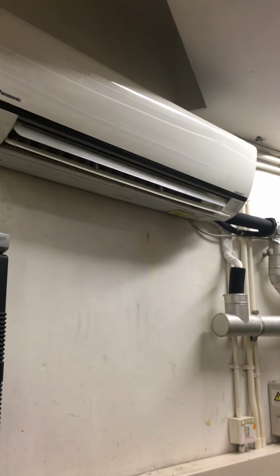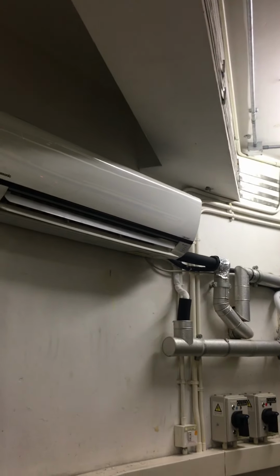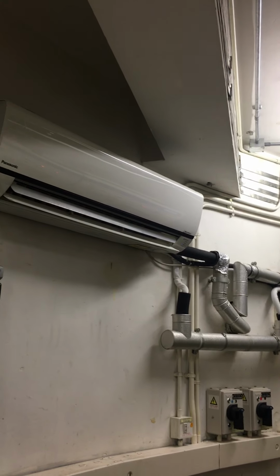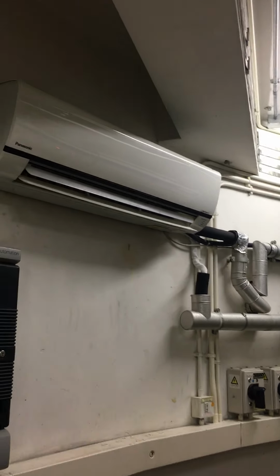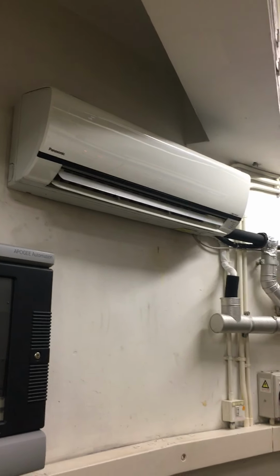So inside the main LV switch room, we may have the air conditioning. And the air conditioning should not be fan coil units because electrical system should be separated from water. So instead of fan coil units, split type air conditioning is used. So in case of leakage, the refrigerant will be vapor, but not liquid. Okay. So this is behind the main LV switchboard. So you see we need to leave some maintenance space behind the switchboard.